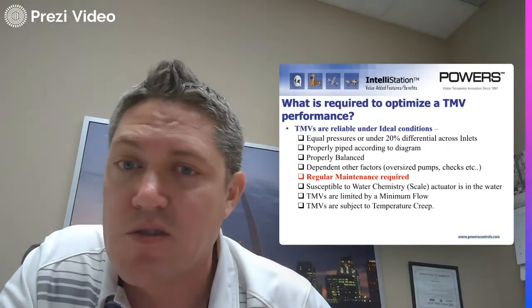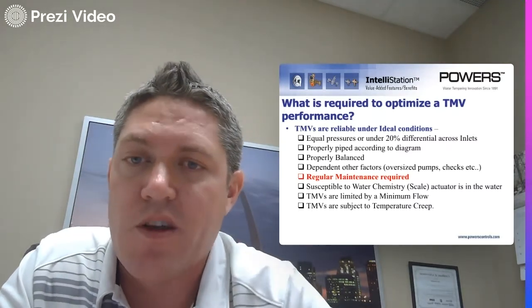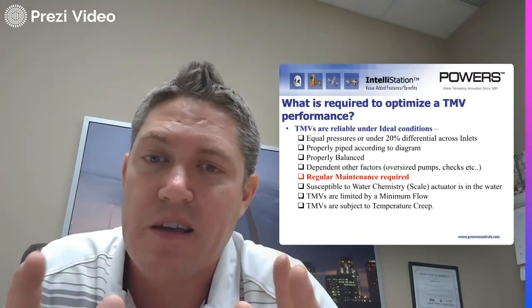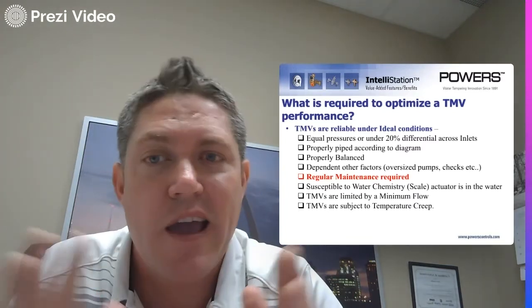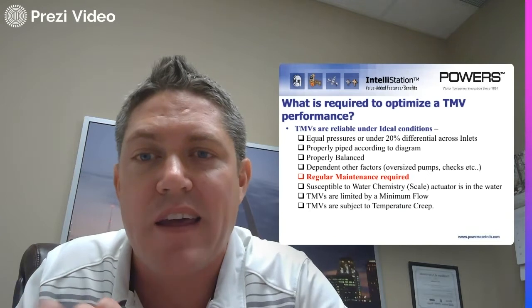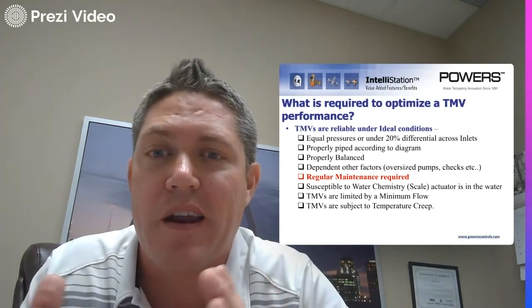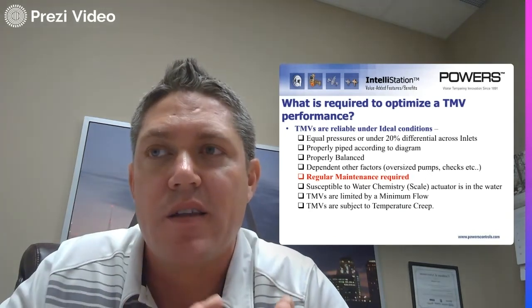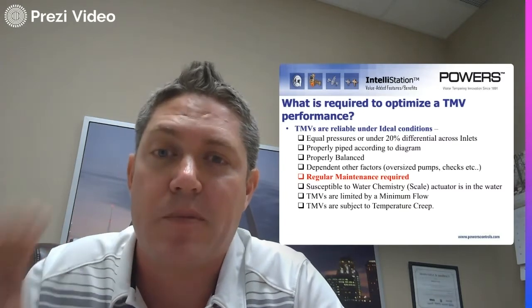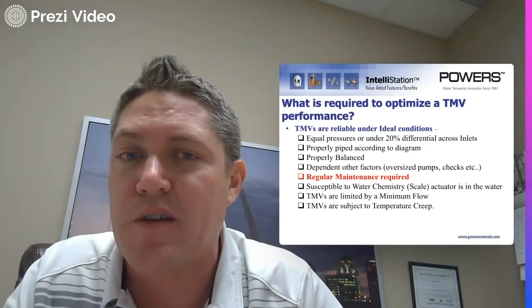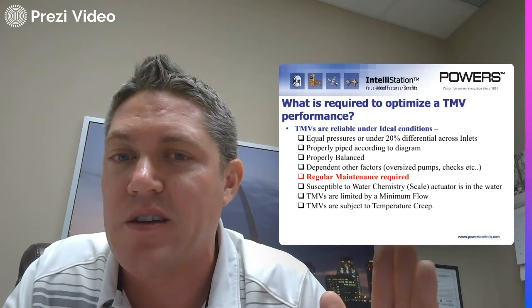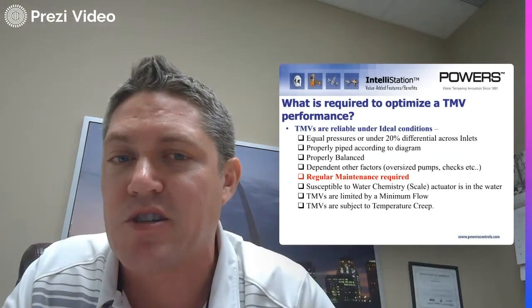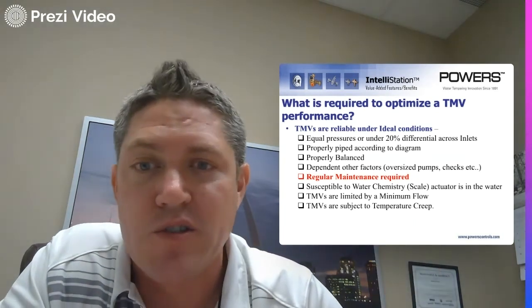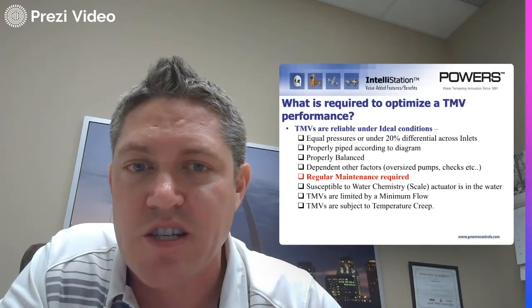If too much of it goes back to the water heater, well, then you're going to get temperature creep. And that mixing valve will try to adjust and say, hey, it's too hot. It'll start to close off the hot inlet. But because it can only close off about 80% one way or the other, it's still going to be able to allow flow on that side. If too much is being forced back towards the heater by that recirc pump, that's when you're going to get your temperature creeping up overnight when no one's using water and you're in a closed loop situation.